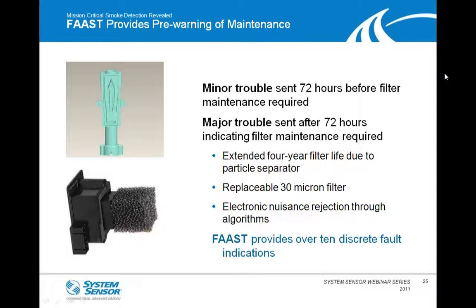After those 72 hours, if that situation hasn't been rectified, the filter hasn't been cleaned or replaced, a major trouble would occur. And what this allows you to do is basically provides you that type of discrete information you need in order to agree with the standard that we just read as far as trouble conditions. In addition, our filters actually have a much longer life than a lot of the competitive products, which rate them at about 2 years. We're rating our replaceable filter at about 4 years.